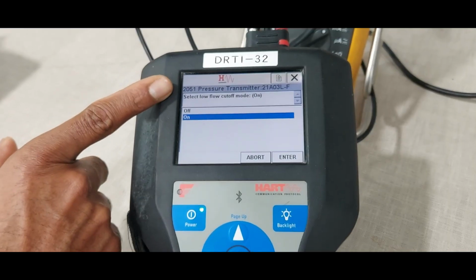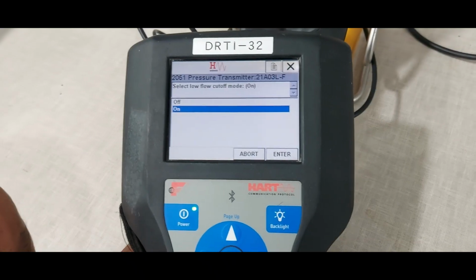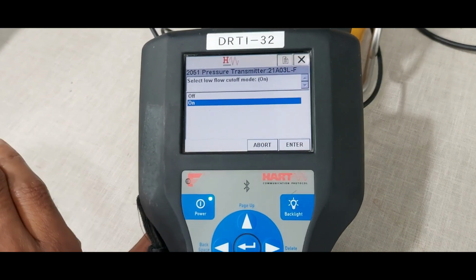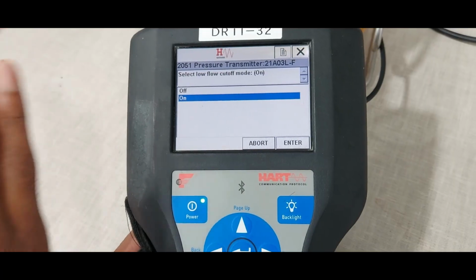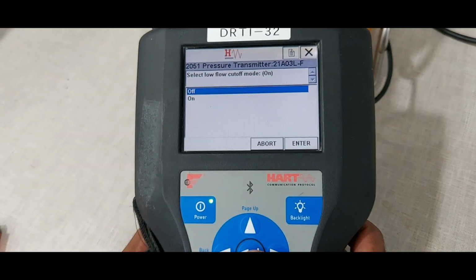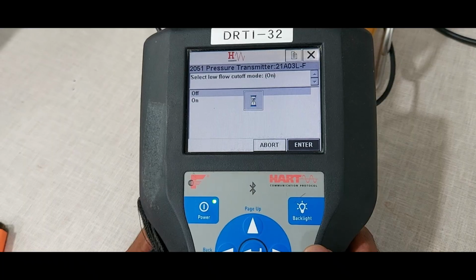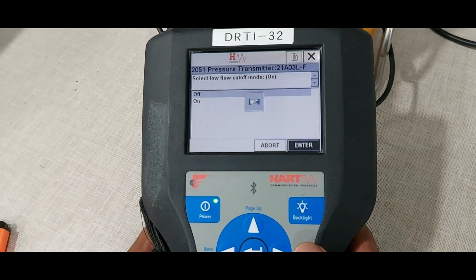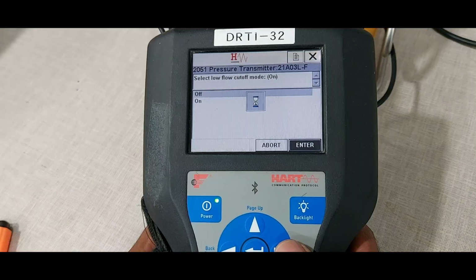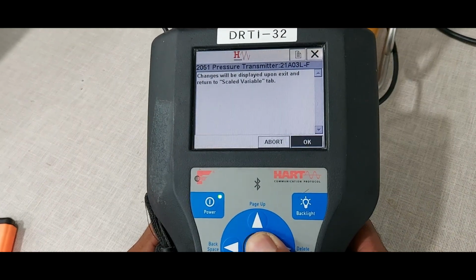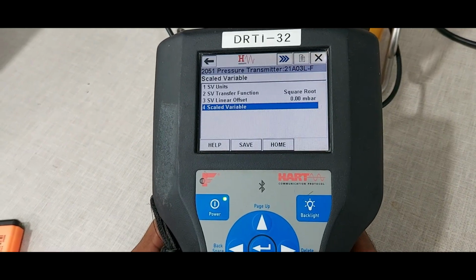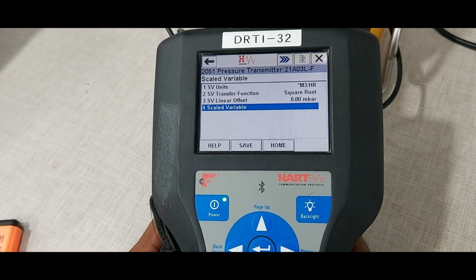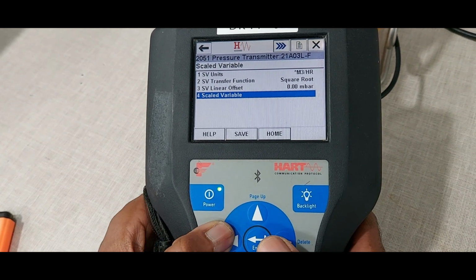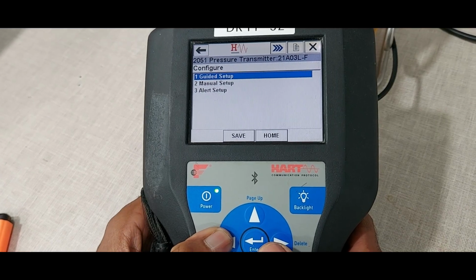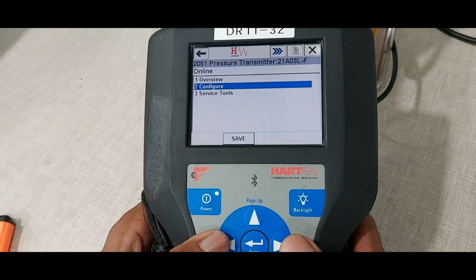Next one option is there. Select the low flow cutoff mode. If you require the low cutoff, you can enable the on mode. If you do not require the low cutoff, you can select off mode. Now we are selecting the off mode condition. In the data sheet, no flow cutoff is mentioned. Okay, exit. Okay. Back. Now scaled variable configuration is completed.